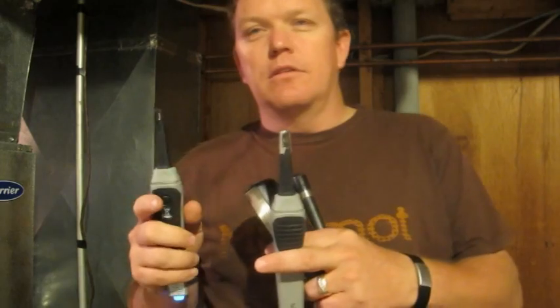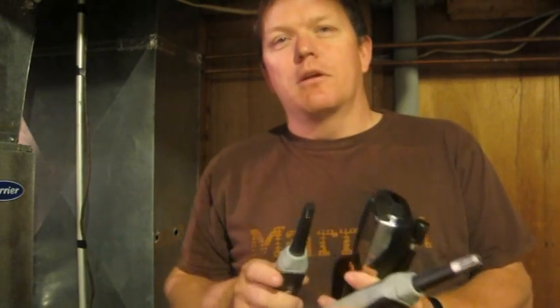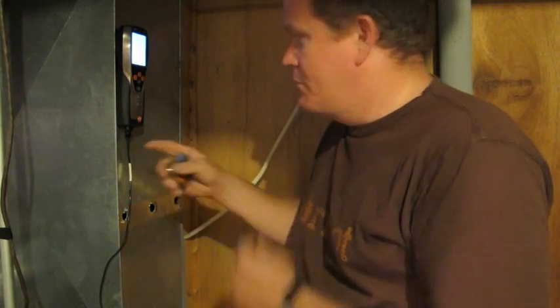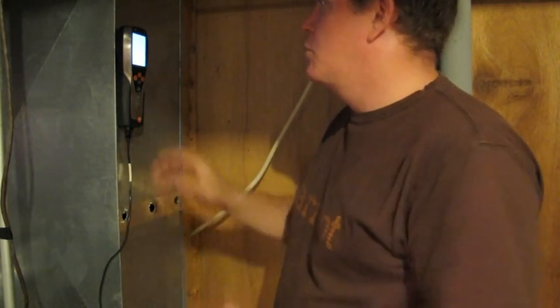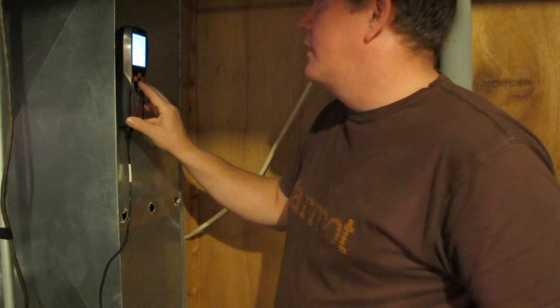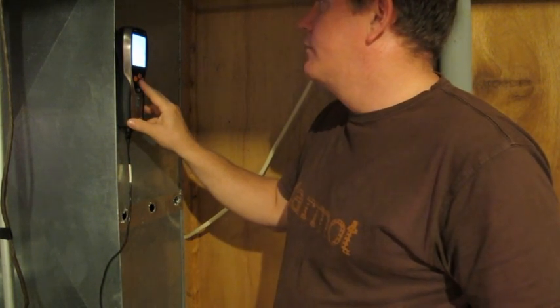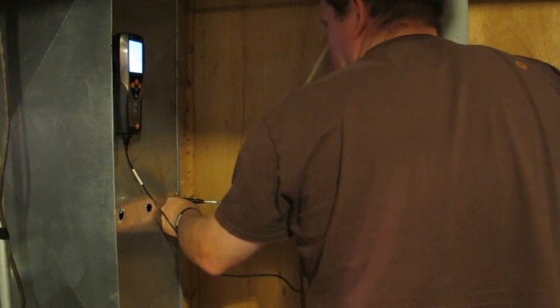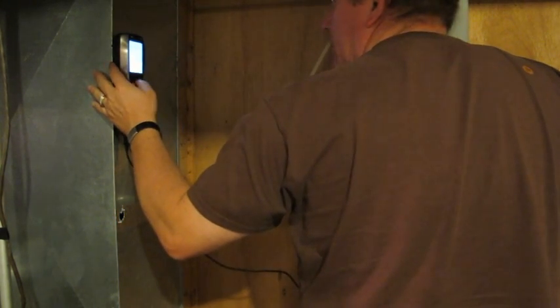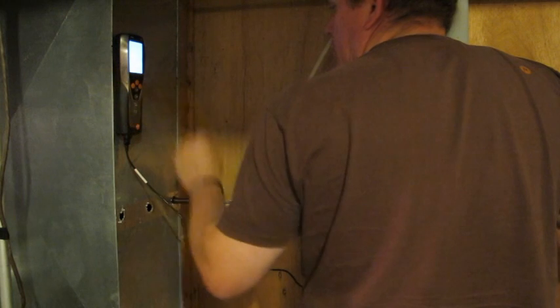I've got the two probes, one for the supply and one for the return. I'm going to stick these in the ductwork, then measure my airflow. The next thing you have to do is measure your return air duct. Mine's 10 by 25, and I'm going to enter that into my 435 here. Now I'm going to measure airflow. I'll hit mean, go timed, and hit start.